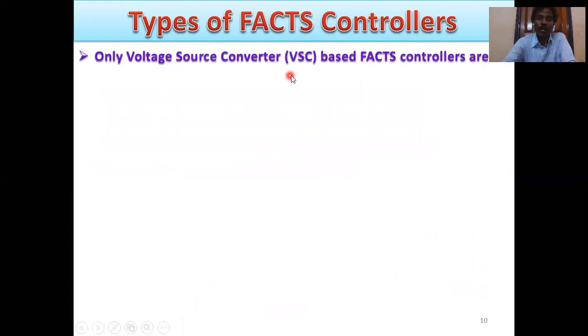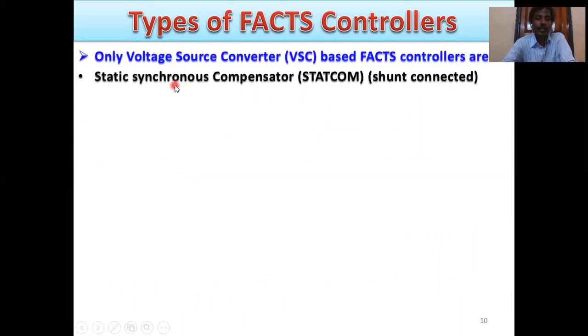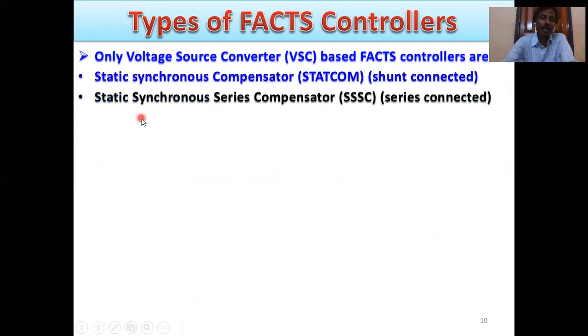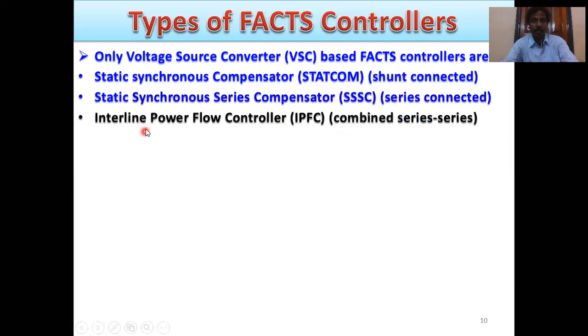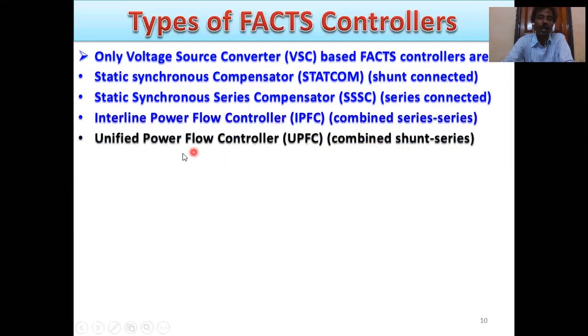The voltage source converter based FACTS controllers are the static synchronous compensator, that means STATCOM. This is shunt connected. Another is the static synchronous series compensator, SSSC, series connected. This is a voltage source converter based FACTS controller. Another is the interline power flow controller, IPFC, a combined series controller. The unified power flow controller is also a voltage source converter based FACTS controller, a combined shunt and series connected FACTS controller.